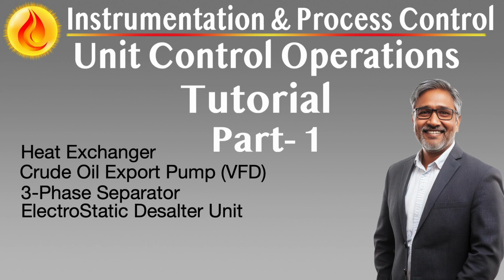Energy efficiency is a key advantage of VFD-based systems. Rather than operating pumps at full speed continuously, power consumption scales roughly with the cube of the speed. Even small reductions in RPM can yield substantial energy savings. Modern VFD systems now support regenerative braking, which captures and returns energy during deceleration or shutdowns. Combined with power monitoring and analytics dashboards, operators can track real-time energy KPIs and align pump performance with sustainability goals.